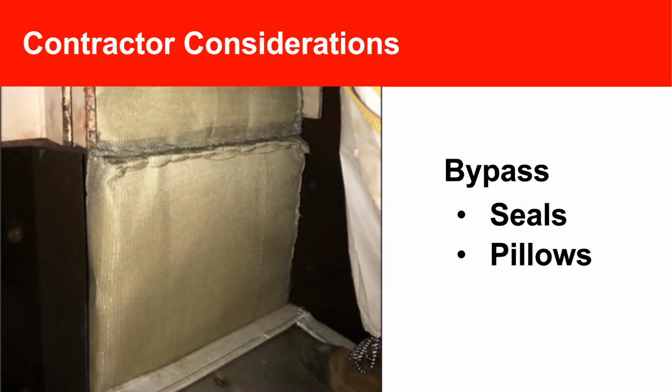Directly behind that, directly downstream of that, is that big pillow material you see. This picture was taken during a catalyst installation project that we were on. The next module was going to be installed right where the person is standing, you can see in the picture. You can notice the pillow has a large depth to it, which creates a large surface area, which increases your ability to seal the reactor as that thermal expansion compresses that pillow over that surface area.